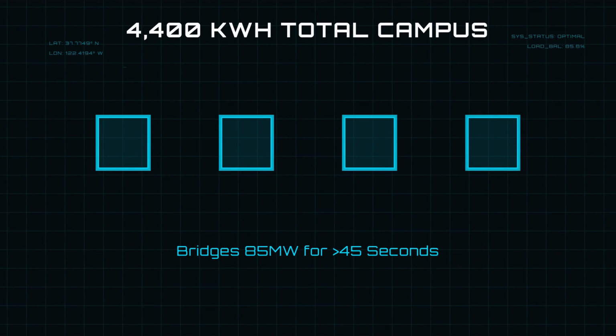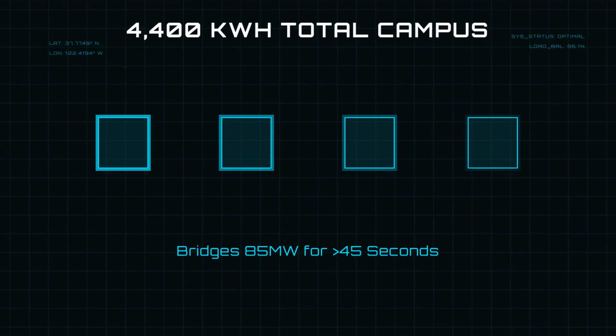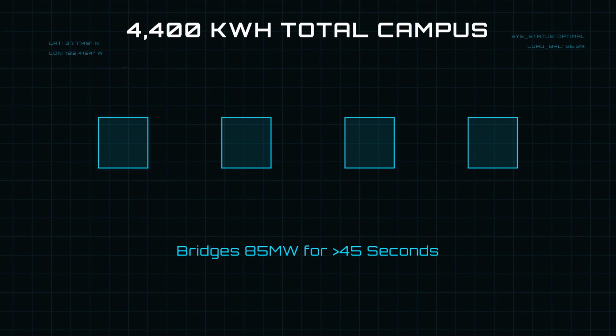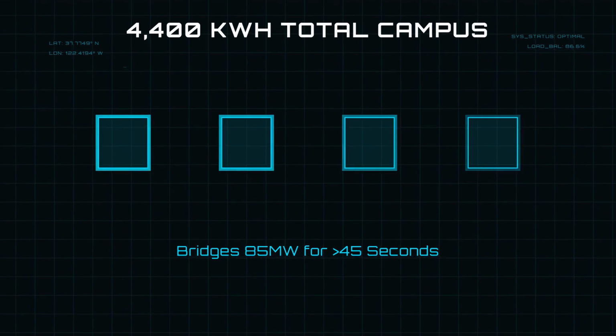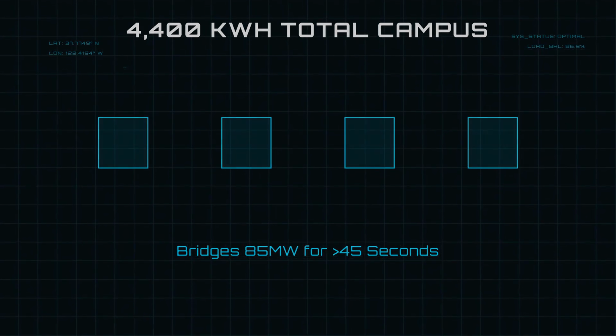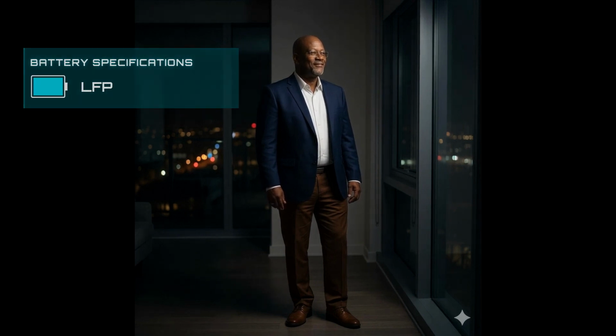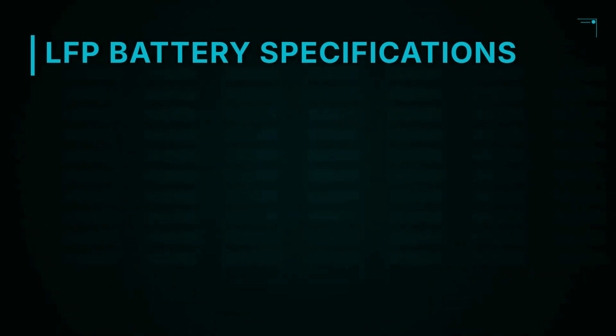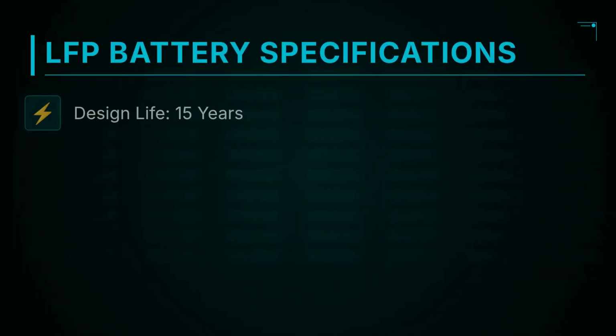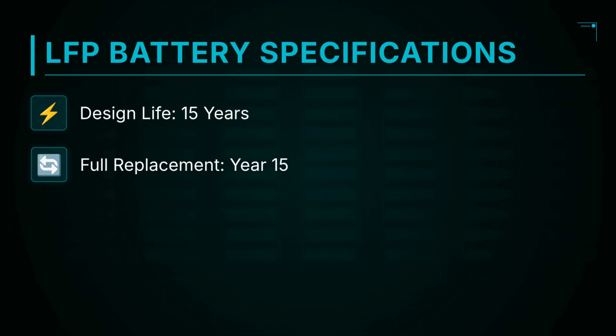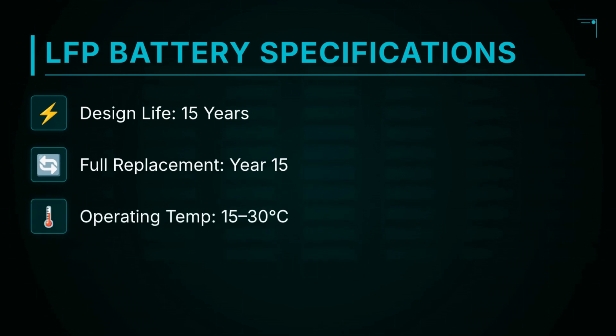This system can bridge 85 megawatts for over 45 seconds even under aged conditions, providing a massive safety window for generator synchronization. This is engineering at scale. For our energy storage, we've specified lithium-ion LFP technology. Lithium iron phosphate offers significantly higher thermal stability than traditional NMC chemistries, making it the only acceptable hyperscale standard for our mission. The design life is 15 years to 80% rated capacity, with a full campus-wide replacement planned at year 15. Temperature control is absolute.